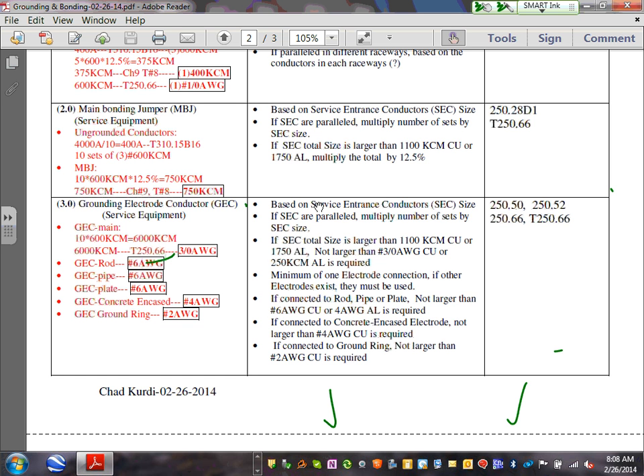Here's my 4,000 amp switchgear divided by 10 parallel. Get you 400, go to 310.15 B16. That will get you 10 sets of 3 conductors, 600 kcm. If you guys don't know how to size these, ask me for a refund. I'm not kidding you, because this is your 3rd project. If you don't know how to take an amp to 310.15 B16 and size a conductor, we didn't do you a favor.